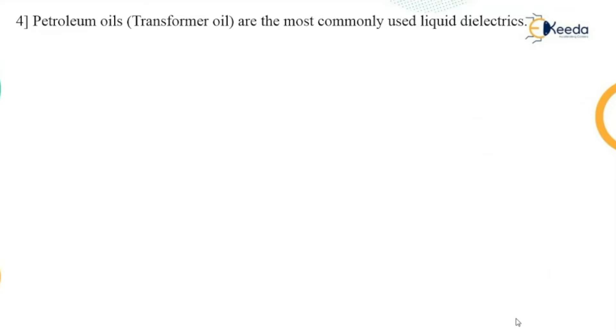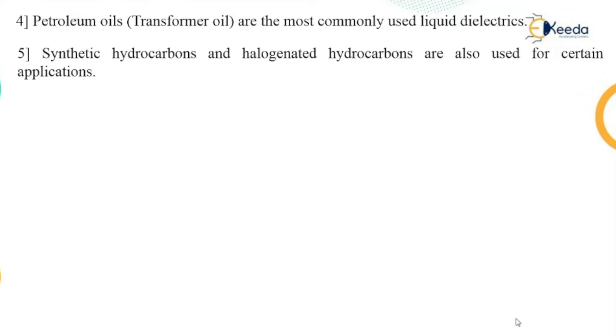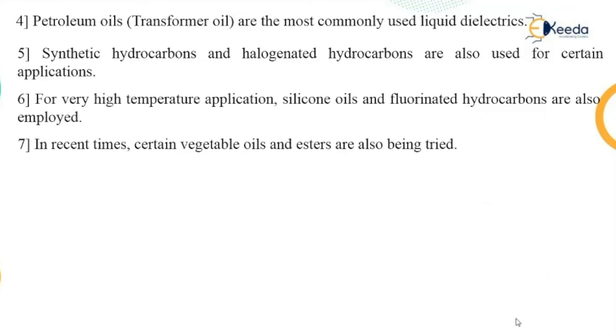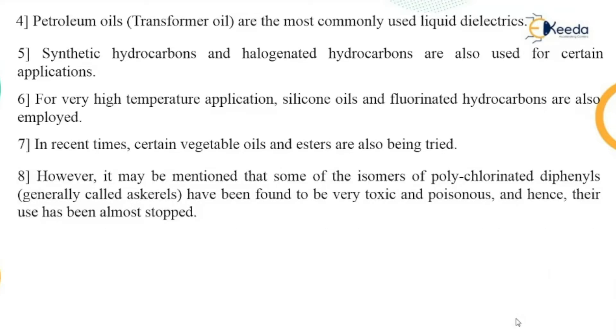There are different oils used — mainly transformer oil, which is used in transformers. It is a petroleum oil but named as transformer oil. There are also synthetic hydrocarbons and halogenated hydrocarbons which have certain applications. For very high applications, silicon oils or fluorinated hydrocarbons can be used. In recent years, vegetable oils or esters have also been tried. However, it must be mentioned that some isomers of polychlorinated diphenyls (PCBs) have been found to be very toxic and poisonous, and therefore they have been stopped from use.